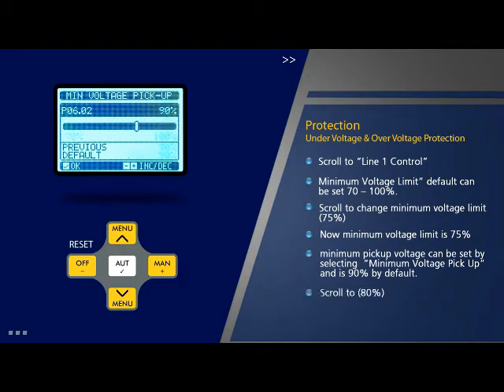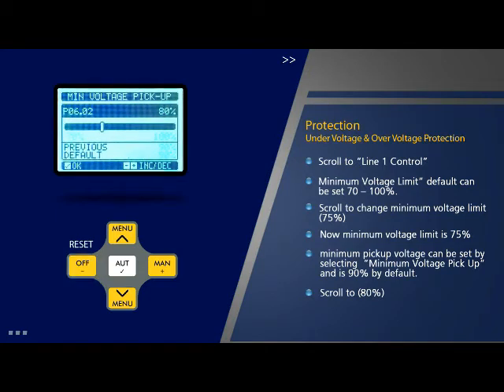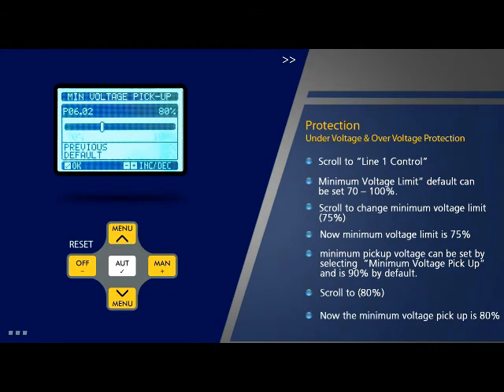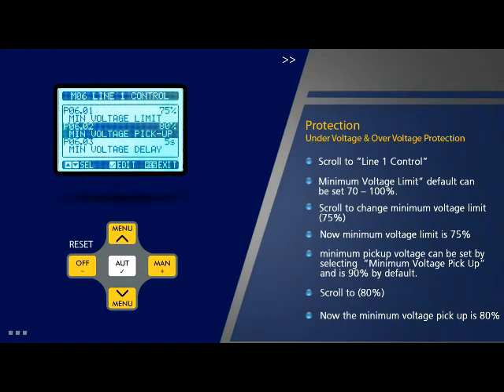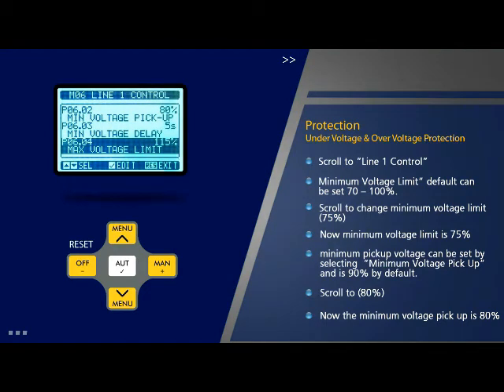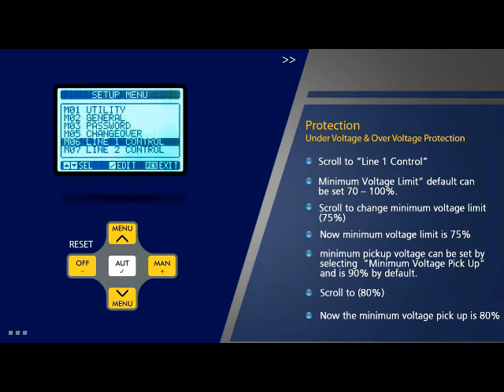Scroll to change the minimum voltage pickup value, for example to 80%, and press OK. The minimum voltage pickup is now changed to 80%. The minimum voltage pickup is also known as hysteresis restore voltage. The values for over voltage and the related maximum pickup voltage can be similarly set using parameter options 4 and 5 on the line 1 control page.